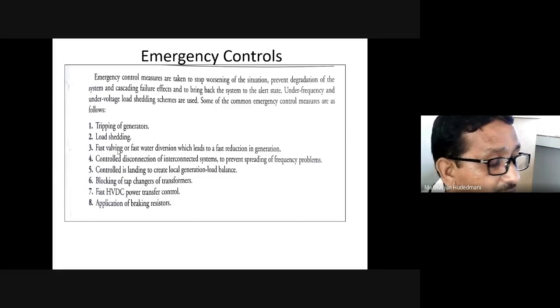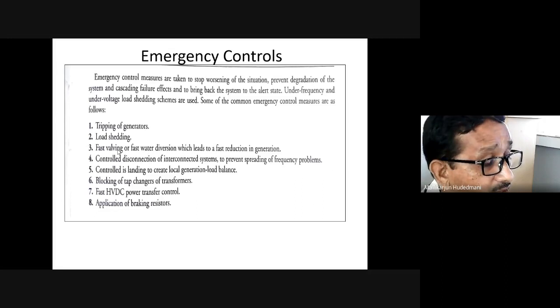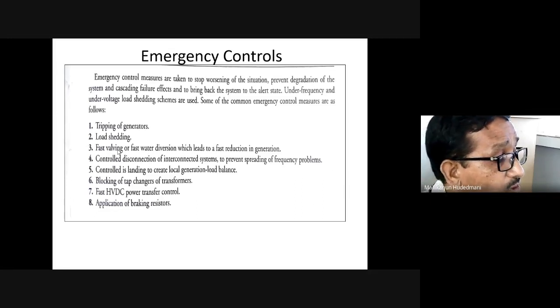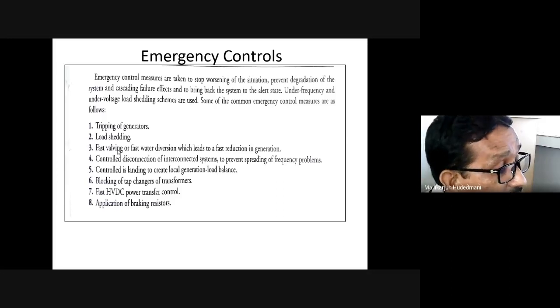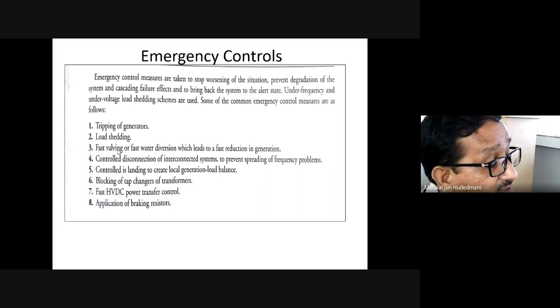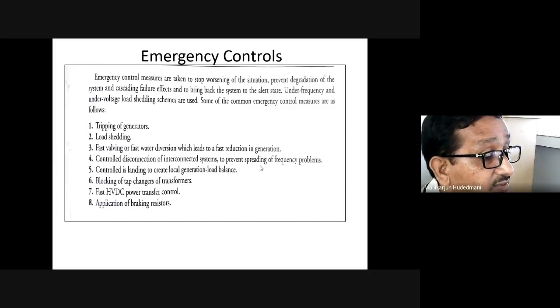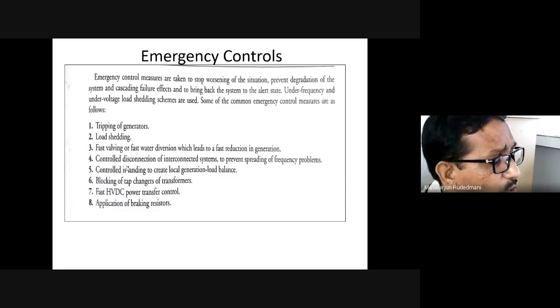Another important fact I would like to discuss with you. As there is a tremendous demand in the particular requirement, the quite natural phenomenon is to raise the input fuel. If there is a dip in frequency due to the additional load megawatt, the frequency has fallen down. The countermeasure in the control system is to increase the input fuel, open the valve so that more fuel enters the turbine blades and the turbine accelerates more and more. If the load on the power system increases, definitely frequency falls down. That demands more input. So more and more opening of the valve makes a runaway speed in the mechanism, which is dangerous. These rotating machines may get damaged. Therefore, when there is a tremendous demand, the valving has to be done properly, diverting and controlling the generation.